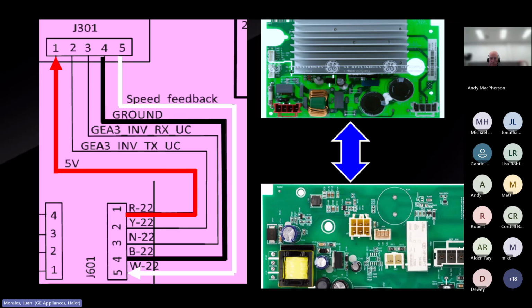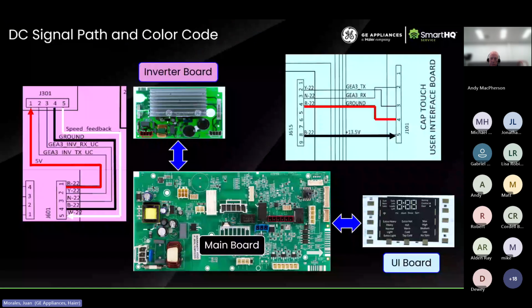The fact that you can check continuity between pins 5 and 5 on these two connectors would basically rule out the possibility of a bad wire harness, and that's why I'm showing you this, because it is important. The machine could just stop working altogether, not because the motor's broken or because you have a bad inverter, but because that signal is not getting to the main. That means the main cannot possibly know what's happening if something bad were to happen, like the machine going out of balance or spinning too fast or too slow.